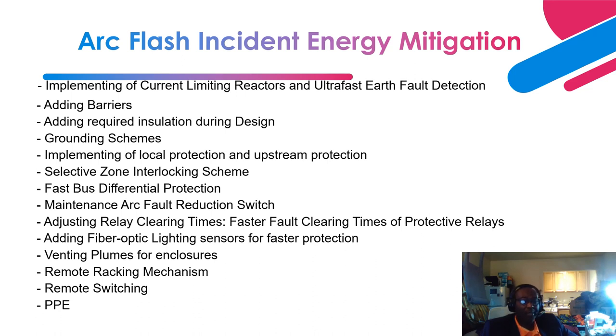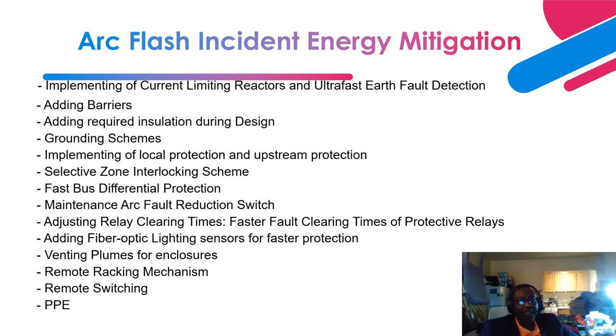Next is implementing local and upstream protection. Upstream protection means having a faster protection scheme on the incomer. Local protection — also called a maintenance mode of arc flash reduction scheme — is utilized to provide faster protection and protect workers when they are working on the switchgear. Next is Selective Zone Interlocking — another fast fault detection scheme where the protection relay closest to the fault sees the fault faster through GOOSE (Generic Object Oriented Substation Event) communication, initiating a trip command to isolate the fault.